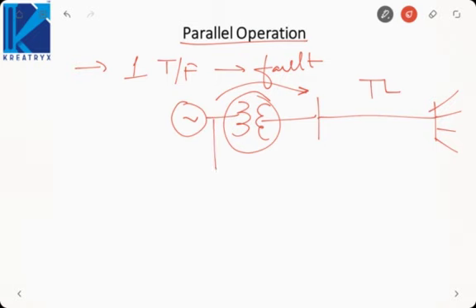But if we connect another transformer in parallel, then what will happen? If this develops a fault, we can disconnect this transformer and current can flow like this. That means we can still supply the load using the second transformer, or the other transformer. Okay, so that is why if there are two transformers in parallel, and one goes out due to a certain fault, the other transformer can take the load and supply the different loads. That is why parallel operation becomes necessary.